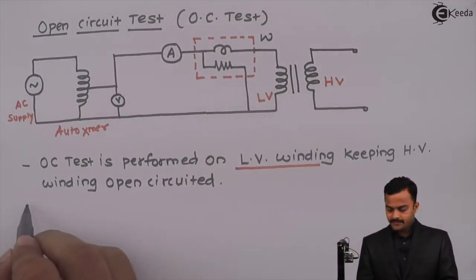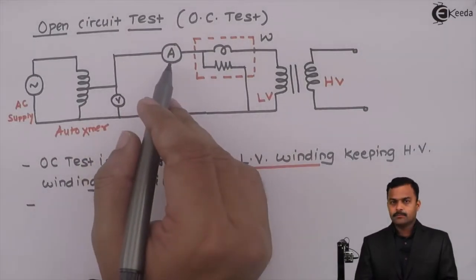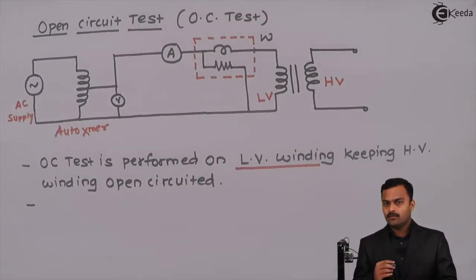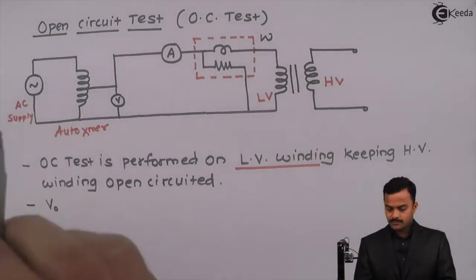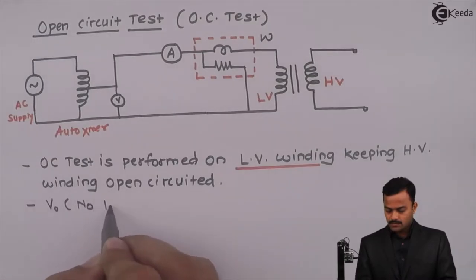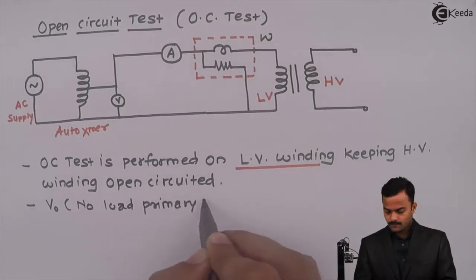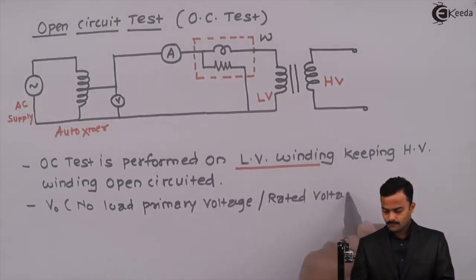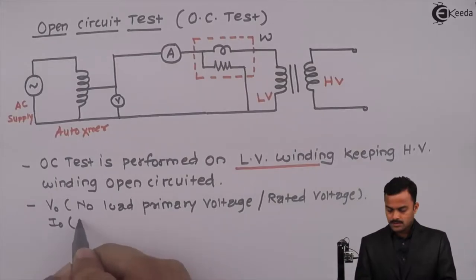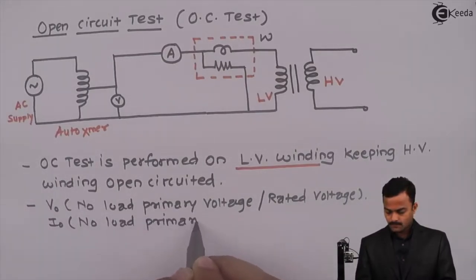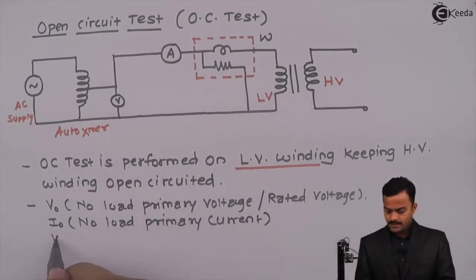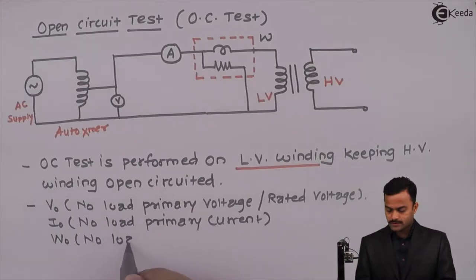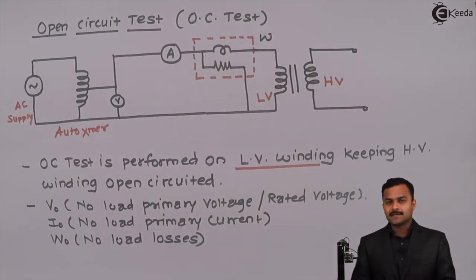The current measured by the ammeter is I0. I will list out all the voltage, current, and wattage. V0 is the voltage, which we call the no-load primary voltage — it will be the rated voltage for the low voltage side. I0 is the no-load primary current, and W0 is the power measured by the wattmeter, which we call no-load losses, or core losses.